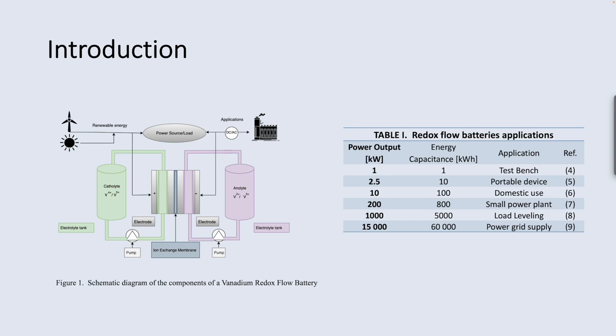The electrochemical cell houses the anode and cathode electrodes and the ion exchange membrane that separates the two electrolyte flows. The anode and cathode electrodes are porous carbon-based materials, and the ion exchange membrane is usually made of a polymer material such as Nafion. During the battery operation, the electrolytes are pumped from the tanks into the electrochemical cell, where the oxidation and reduction reactions occur at the anode and cathode electrodes.